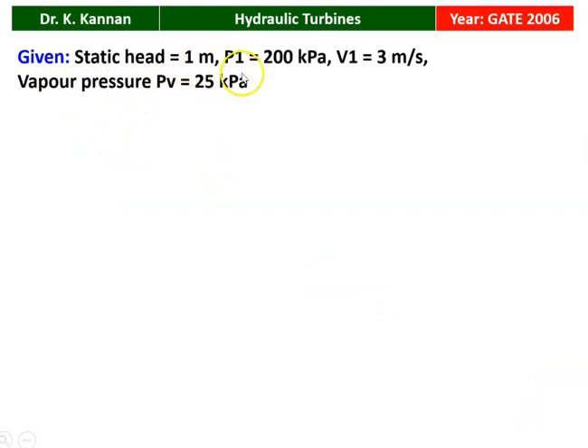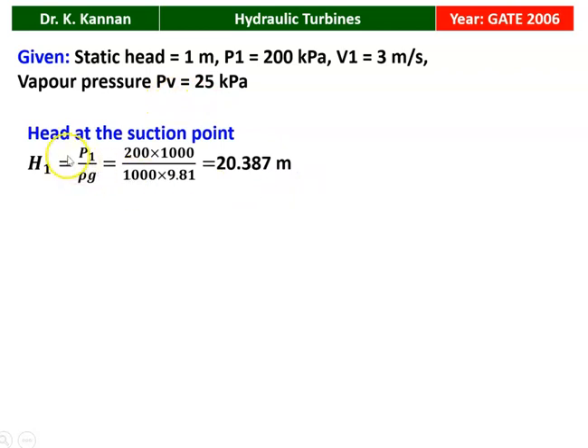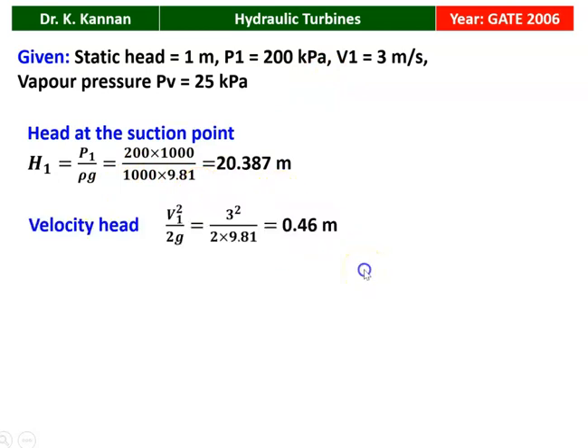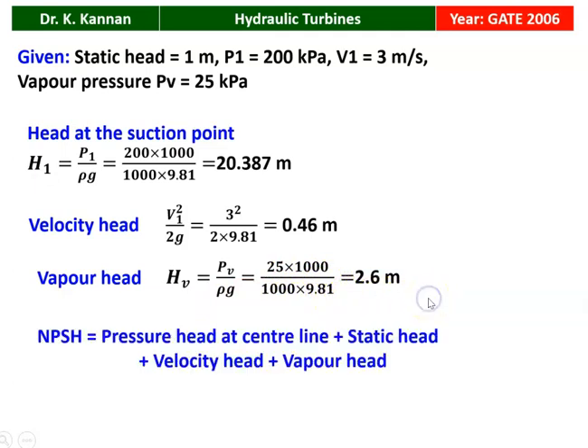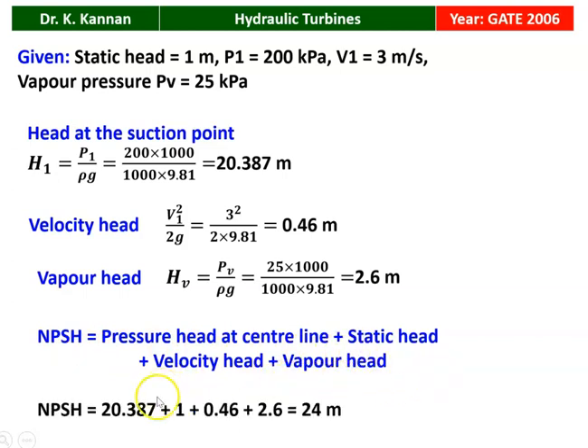Static head = 1 meter, P₁ = 200 kPa, V₁ = 3 m/s, vapor pressure = 25 kPa. Pressure head at suction point: H₁ = P₁ / (ρg) = 200,000 / (1000 × 9.81) = 20.387 meters. Velocity head: V₁² / (2g) = 3² / (2 × 9.81) = 0.46 meters. Vapor head: P_v / (ρg) = 25,000 / (1000 × 9.81) = 2.6 meters. NPSH = pressure head + static head + velocity head + vapor head = 20.387 + 1 + 0.46 + 2.6 = 24 meters. That is the answer.